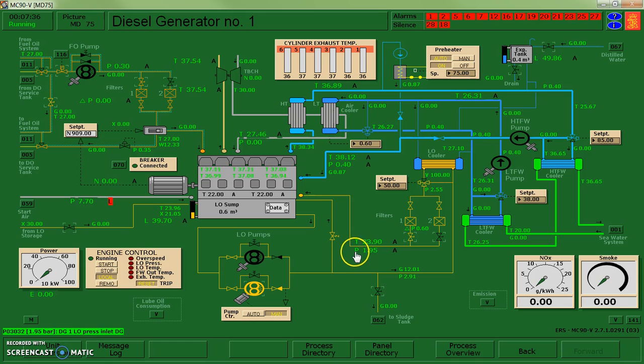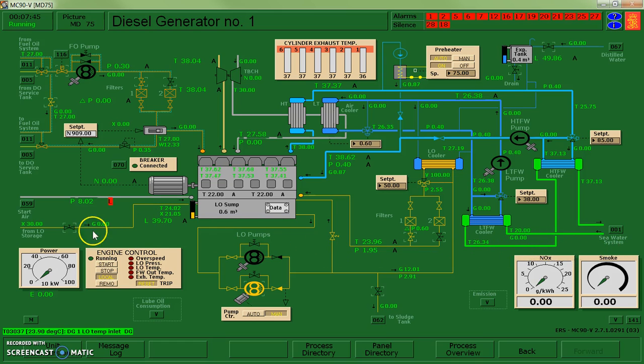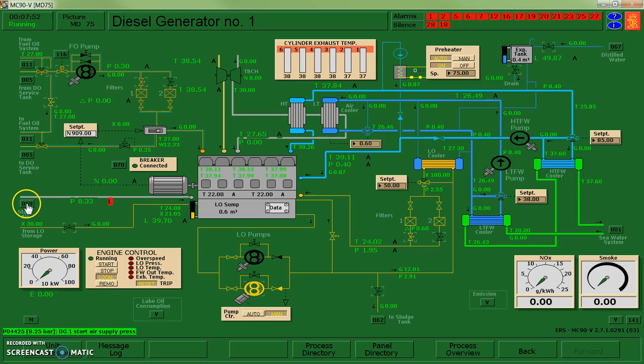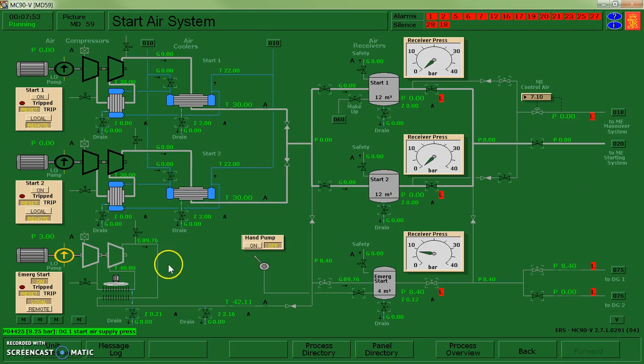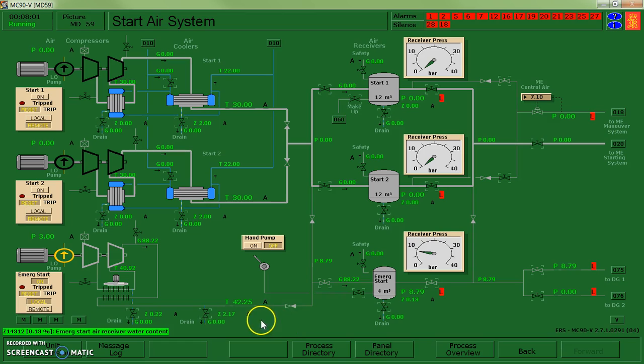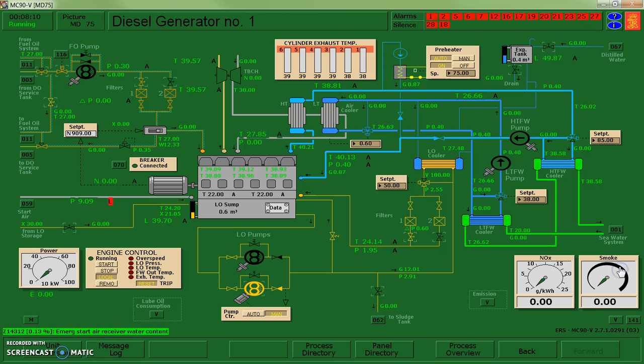So last thing I need to do is look at my seawater system. It's a good idea at this point just to take a look at my air compressors. So I can see I haven't overfilled my air compression system. If I look at my start air system, I'm not overheating. I haven't contaminated it with a bunch of water. So I think I'm okay just to leave that going at this point. I want to keep monitoring it, but I'm okay at this point.